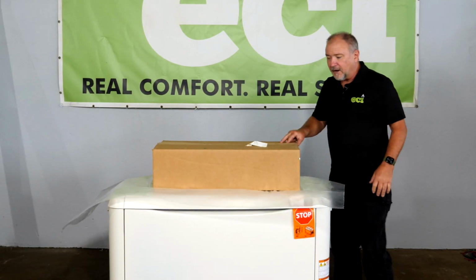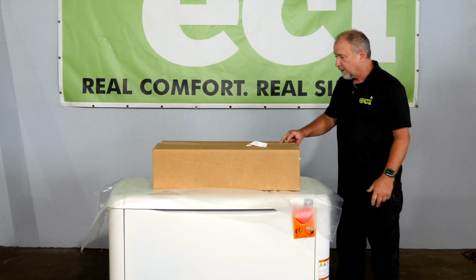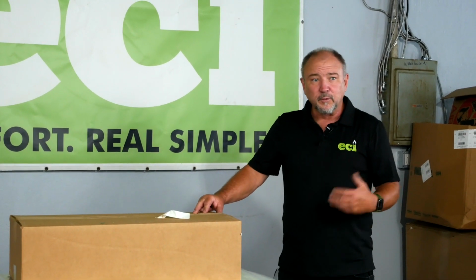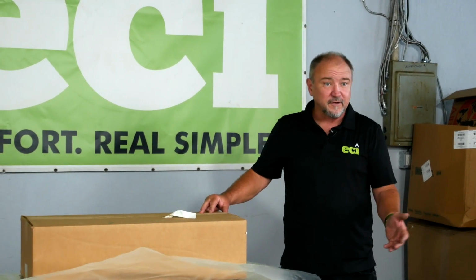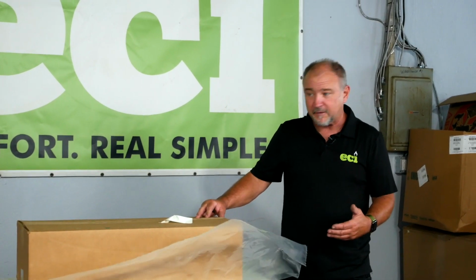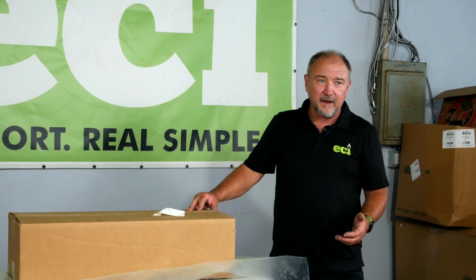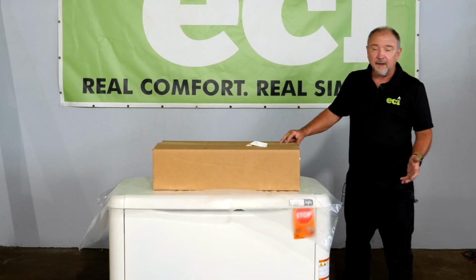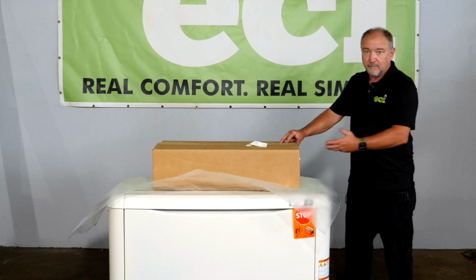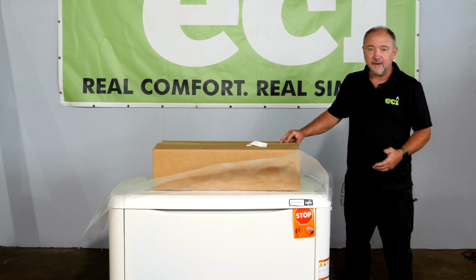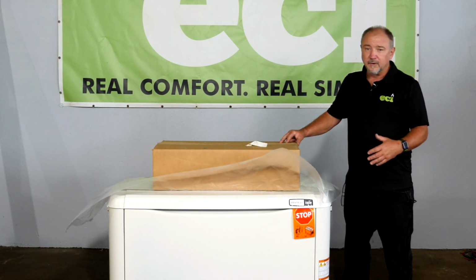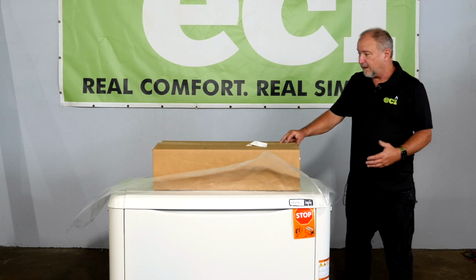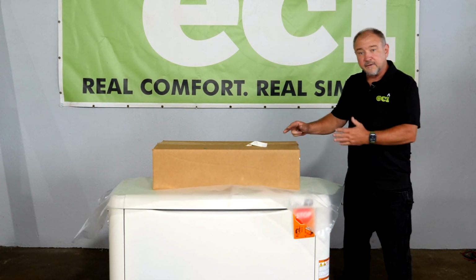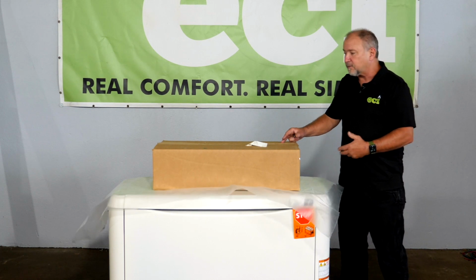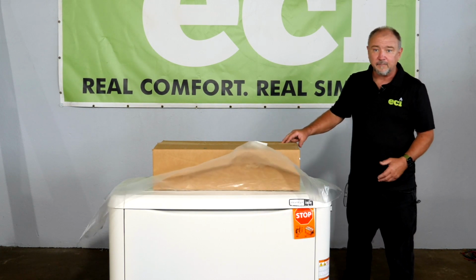So this generator comes with a 200 amp transfer switch. We have to be equal to or greater than the service in your house. If you have 150 amp service, we can use the 200 amp transfer switch. If you have 200 amp service, we obviously use the 200 amp transfer switch. Some older homes might have 100 amp service - you can still use the 200 amp transfer switch, or we can use a 100 amp transfer switch.